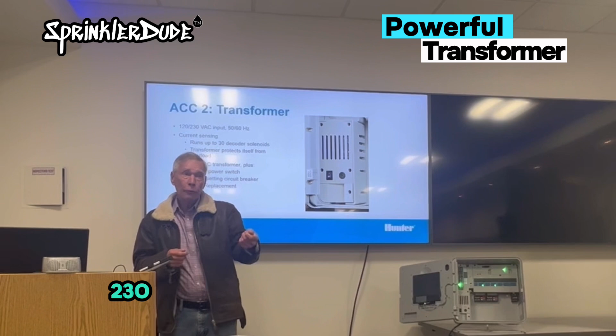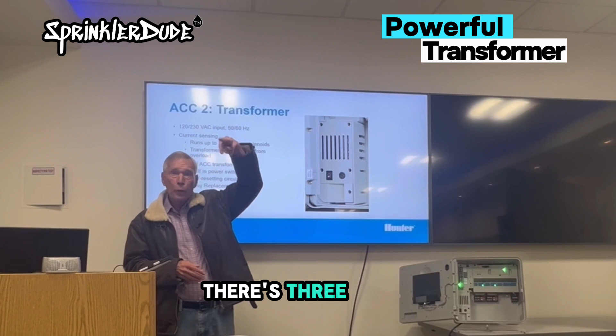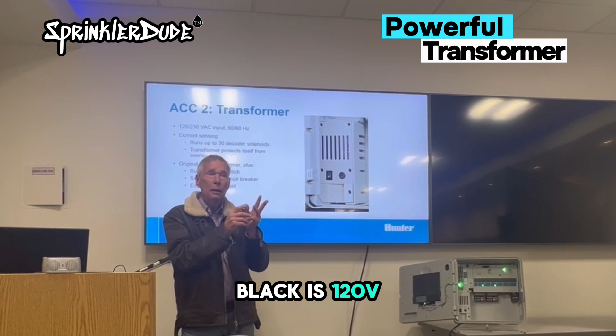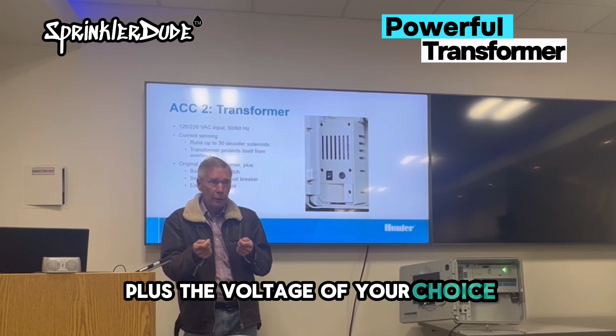The transformer is either/or. It can be 120 volt for the United States, or 230 volt for use on a pump station or for our international customers. There are 3 wires hanging down there. Brown is 230, black is 120, and the blue wire is a neutral. So you use blue plus the voltage of your choice.